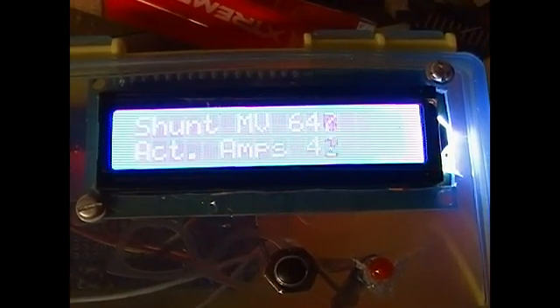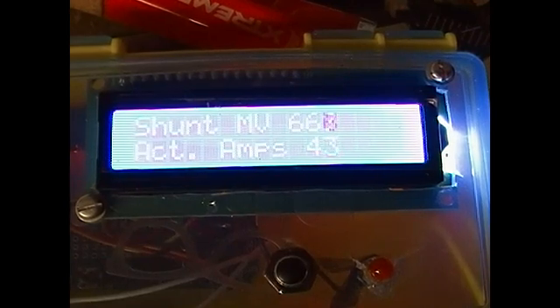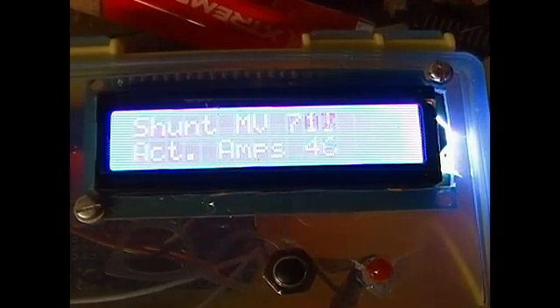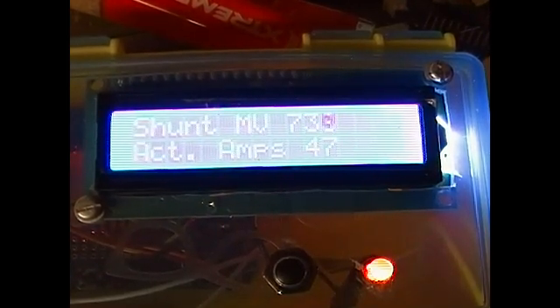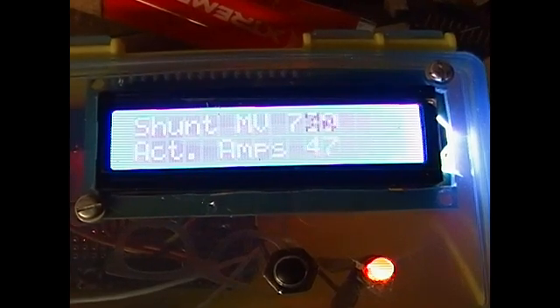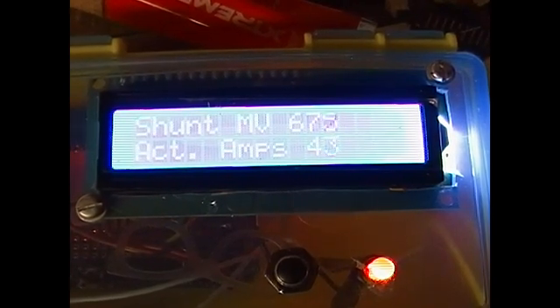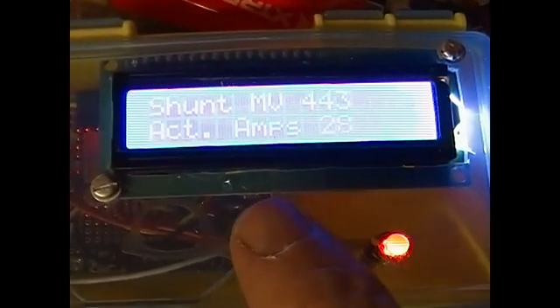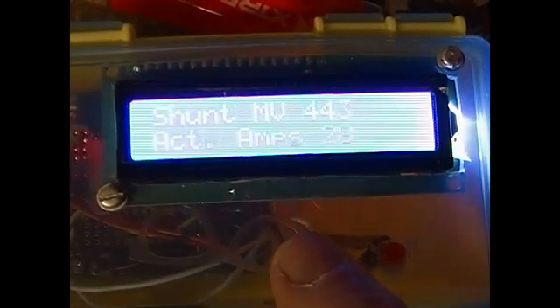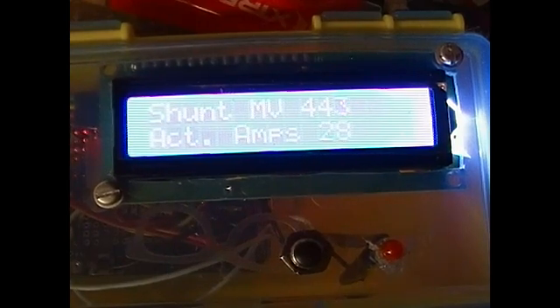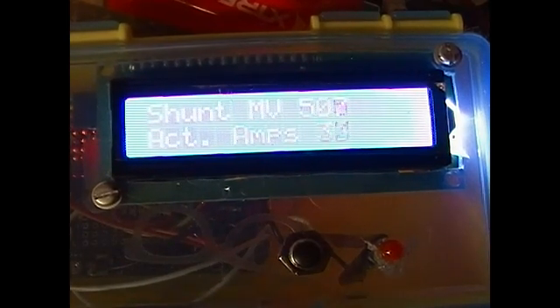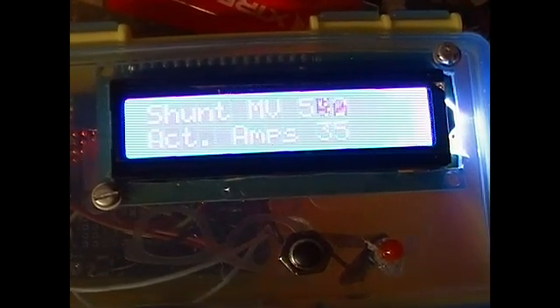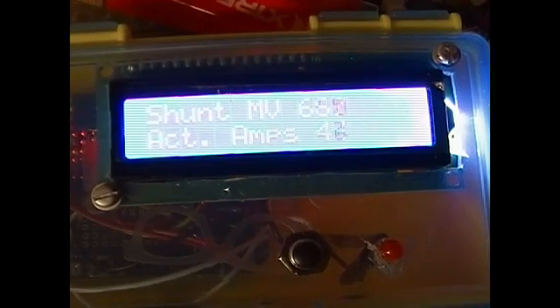That tells me that I have just shut the SSR off and reached the overcurrent setting. There we are, 47 amps. Now I turn the pot back down and the light stays on until I hit the reset button.